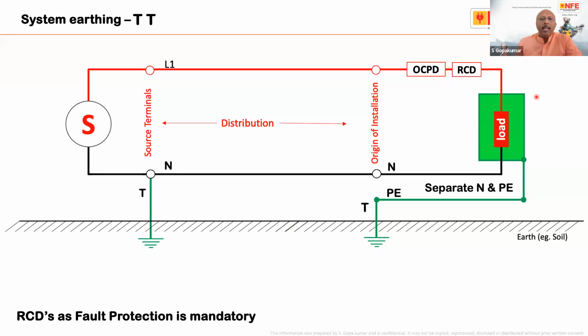Now in case of a fault of negligible impedance, let's say there is a fault in this particular panel or some part of the electrical installation, the fault current goes through the earth electrode, through the soil, and returns back to the source. So now you can see the colored line, which is the route of the fault current. The problem in this case is that two earth electrodes come into series with this loop, resulting in a higher loop impedance. As a result, the fault current will be very less. As a result, the OCPD will not trip. So it is inefficient in tripping.